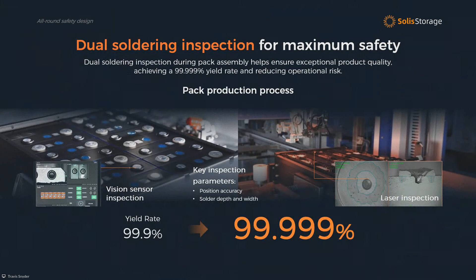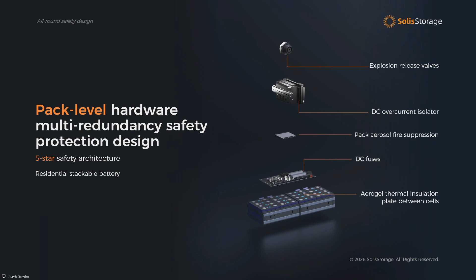Looking at the pack level hardware, we have the explosion relief valve on top, the DC overcurrent isolator, the pack aerosol, DC fuses, and aerogel, which is a thermal insulation between the plates that adds to our safety. We looked at all the manufacturers and basically none of them had DC overcurrent fuses. A lot of them had that isolator, but none had that fuse, which is the extra protection to prevent overcurrent issues, because overcurrent on the battery can actually damage your inverter and cause a double failure.